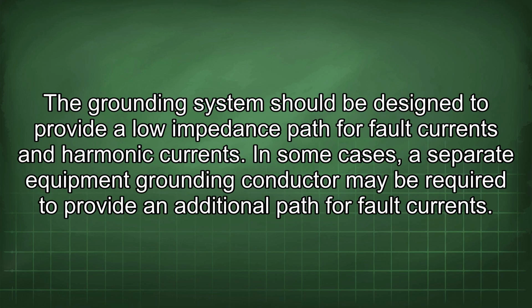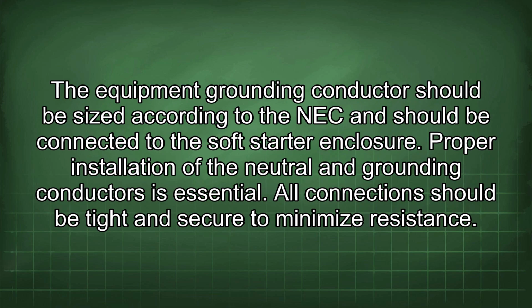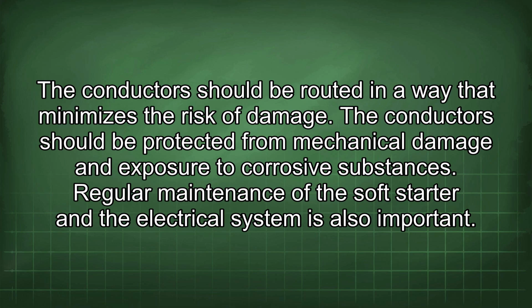The grounding system should be designed to provide a low impedance path for fault currents and harmonic currents. In some cases, a separate equipment grounding conductor may be required to provide an additional path for fault currents. The equipment grounding conductor should be sized according to the NEC and should be connected to the soft starter enclosure. Proper installation of the neutral and grounding conductors is essential. All connections should be tight and secure to minimize resistance. The conductors should be routed in a way that minimizes the risk of damage, and protected from mechanical damage and exposure to corrosive substances.